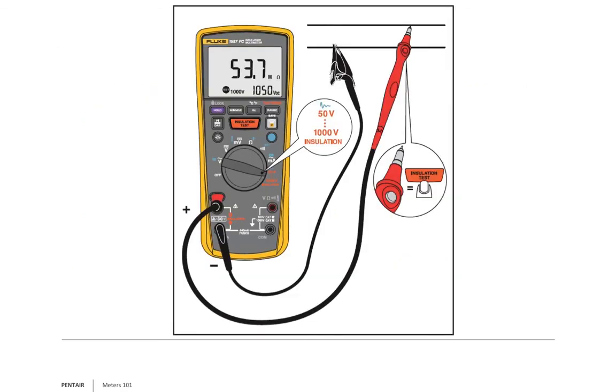Here is that Fluke I was talking about earlier. Depending upon the meter, like in the case of the Fluke 1587, all buttons and markings in orange indicate the insulation test. This one shows nicely the alligator clips. Fluke also has a probe set where, when you're ready to test, you hold the meter in one hand and push the button on the probe. That's okay, but I myself would still put the alligator clip on and then push the button on the meter itself. Because this is an ohms test, I'm not afraid to hold the meter.